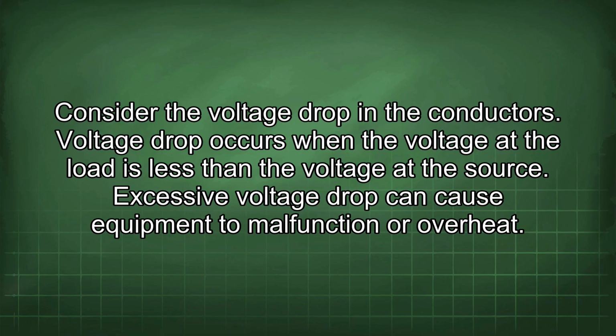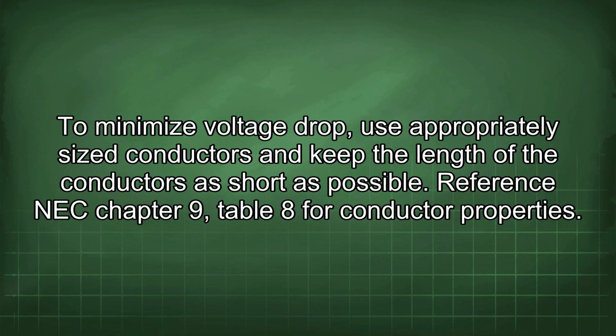Consider the voltage drop in the conductors. Voltage drop occurs when the voltage at the load is less than the voltage at the source. Excessive voltage drop can cause equipment to malfunction or overheat. To minimize voltage drop, use appropriately sized conductors and keep the length of the conductors as short as possible. Reference NEC Chapter 9, Table 8 for conductor properties.